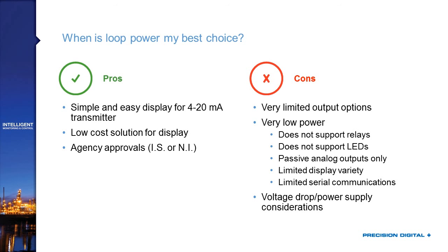You have to keep those cons in mind as well, though. They're only going to work in those situations where you're able to use those limited output options. And because they're low power, you're not going to get the relays. You're not going to get an LED display if that's what's in the spec. You're not going to be able to have a powered 4 to 20 loop coming out of this to retransmit it somewhere else. But if you're okay with those limitations, then there are some definite pros.